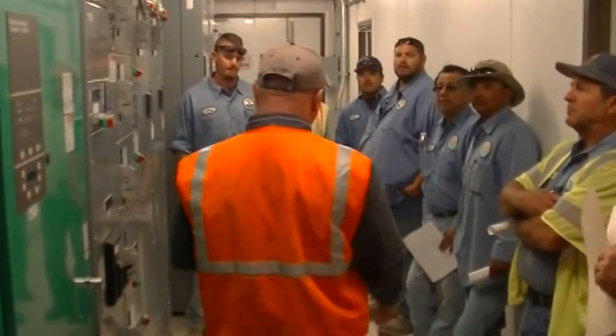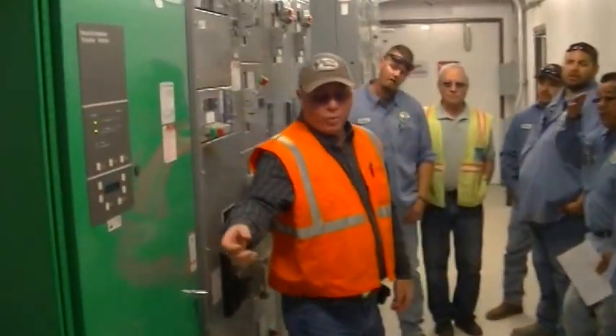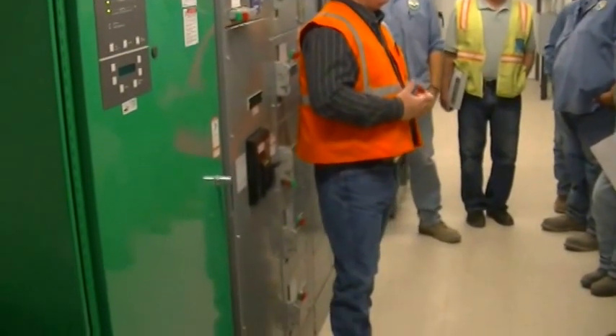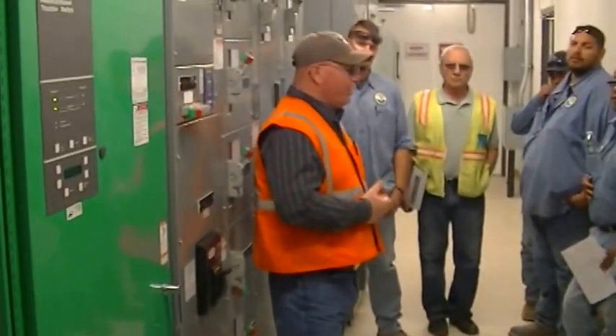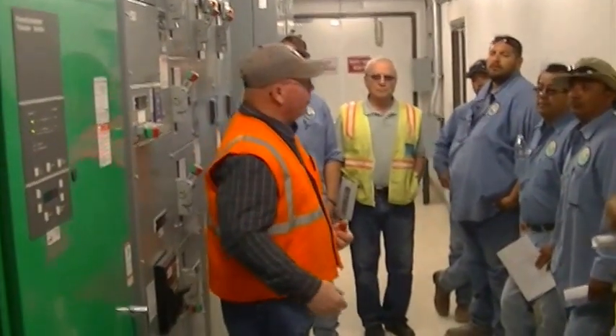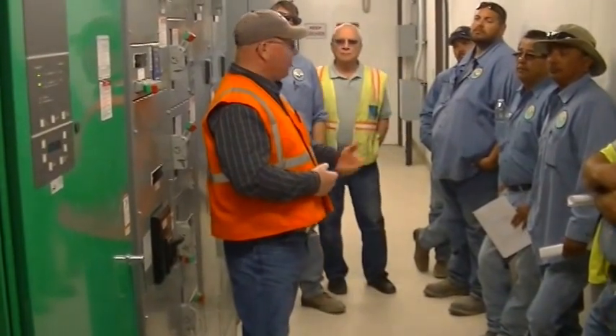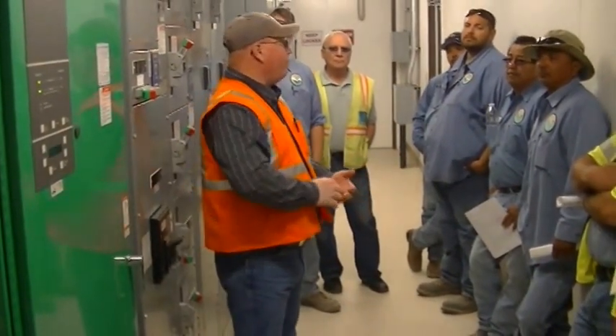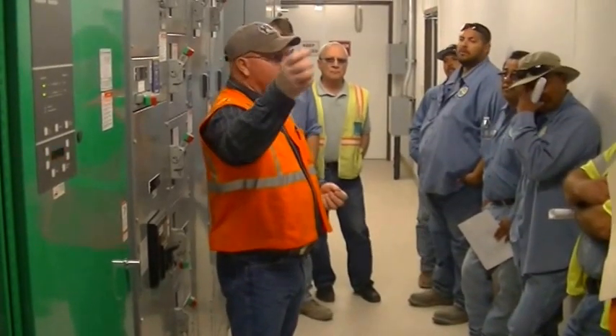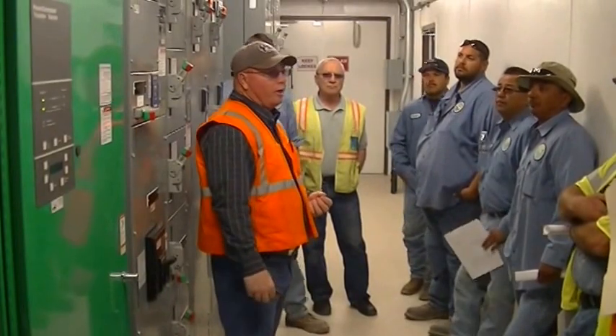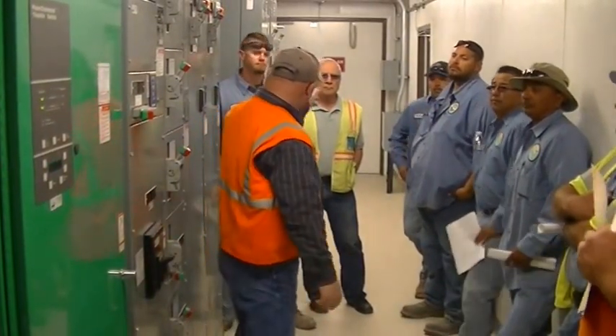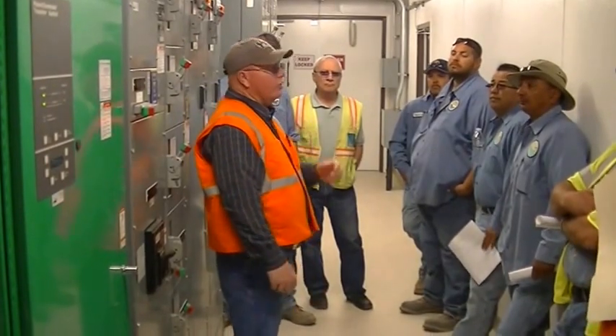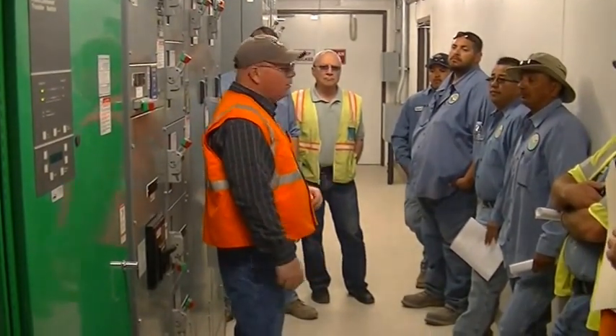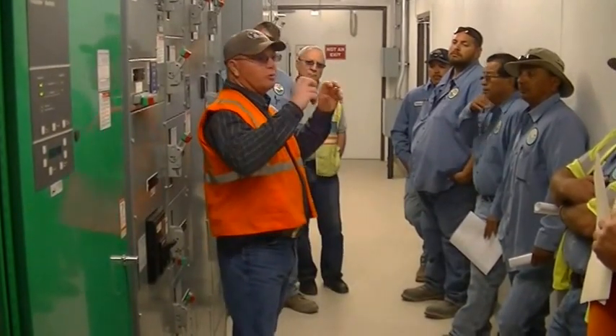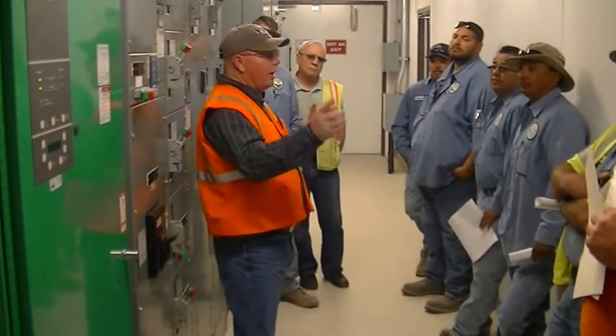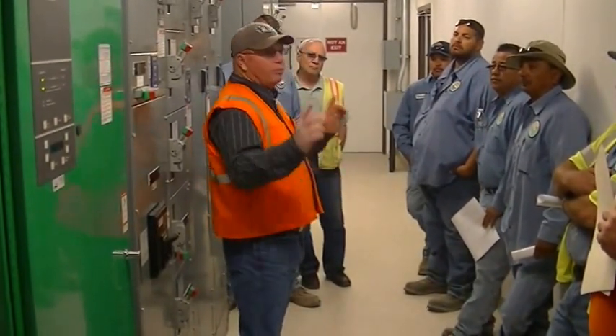I'm Jim Walker with Hydro Controls. Your transfer switch is what's looking at your two voltages. Your utility, which is your power coming in from the utility, and your generator power. If you lose your utility service, it's going to recognize it and swap, and it's going to call for your generator to come up and run. It also signals over to your SCADA system telling you that you've lost your utility service. So it's not what you consider a real smart unit, but smart enough that it'll signal your generator and your SCADA system what's going on.